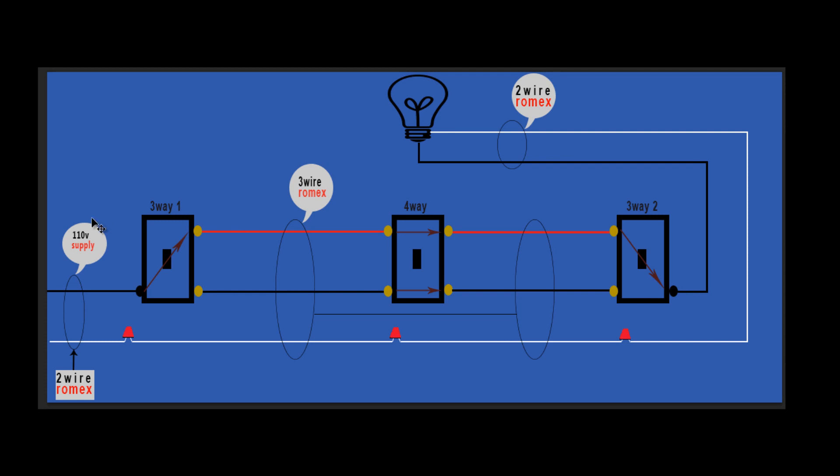So each box has two cables coming in. The first box has the supply cable, which is a two-conductor Romex. Leaving that box and going to the box that contains the four-way switch is a three-conductor Romex cable. And leaving the box that has the four-way switch in it, we have a second three-conductor cable that travels to the last box, which has a three-way switch in it. And in that box, we're going to have that cable coming from the box containing the four-way, and we're also going to have another two-conductor Romex in that box that's going up to the light.